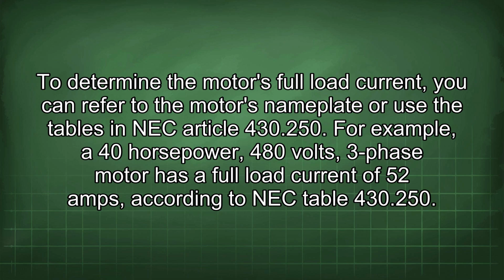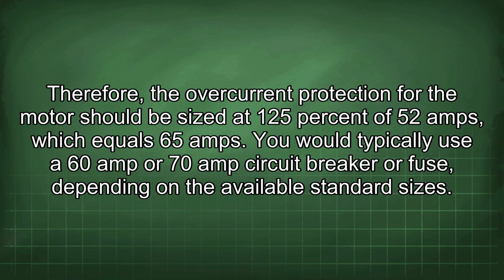430.250. For example, a 40 horsepower, 480 volts, three-phase motor has a full load current of 52 amps, according to NEC Table 430.250. Therefore, the overcurrent protection for the motor should be sized at 125% of 52 amps, which equals 65 amps. You would typically use a 60 amp or 70 amp circuit breaker or fuse, depending on the available standard sizes.